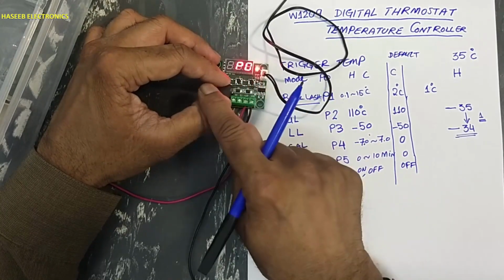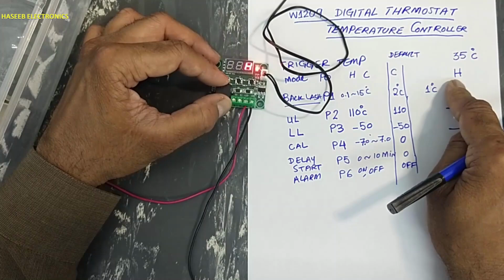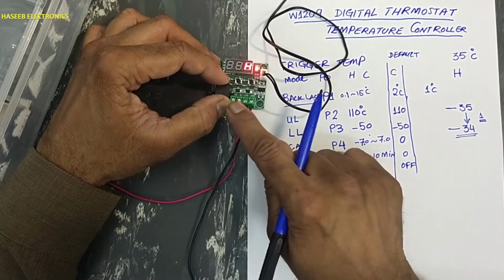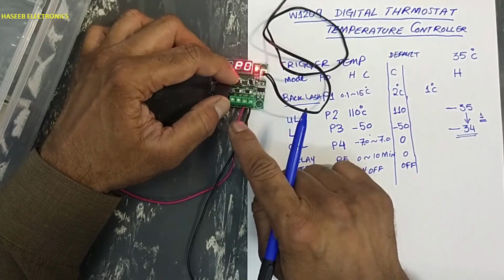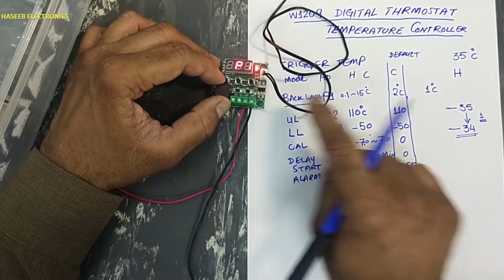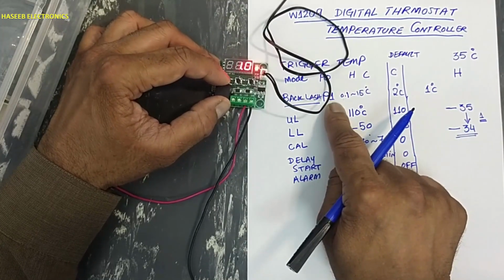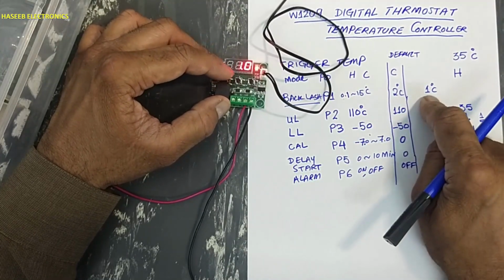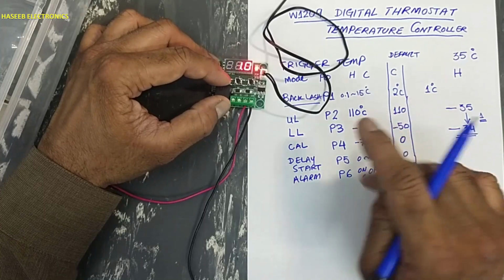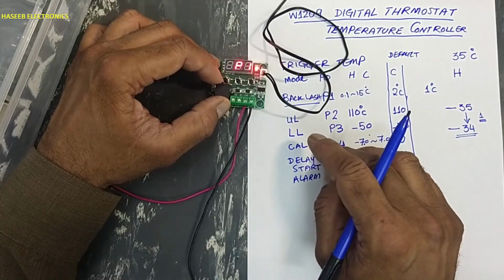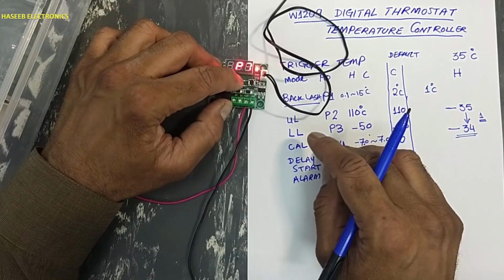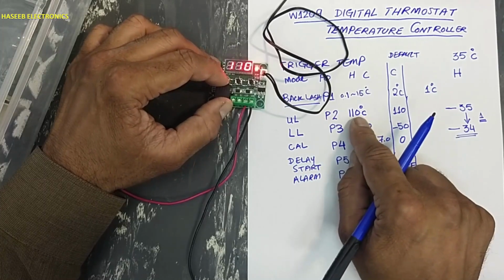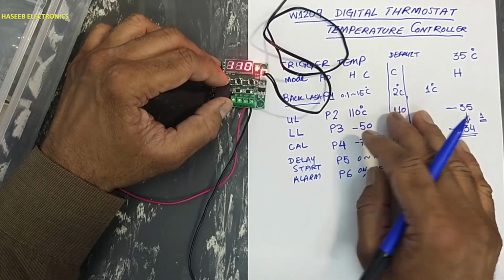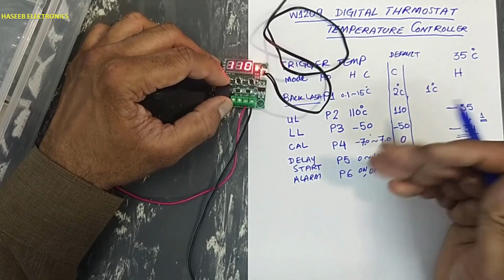P0. Press set button again. It is H. Now we are in heat mode. Press set button. Now P0. Set plus button. Now we are entered in P1 mode. Press 1 degree Celsius. Now this is the backlash temperature. Set button. Now plus P2 upper limit. Normally we don't need to set any upper limit or lower limit.